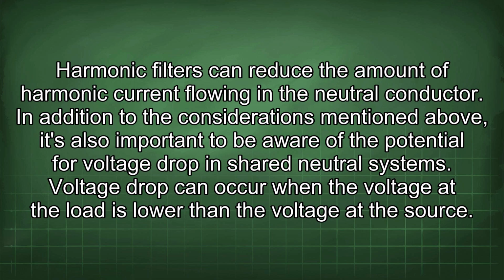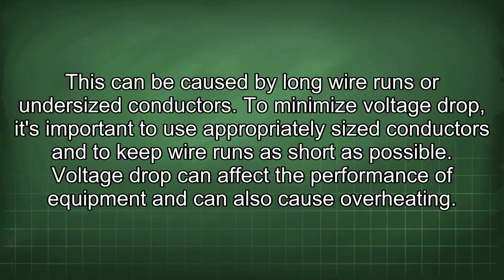In addition to the considerations mentioned above, it's also important to be aware of the potential for voltage drop in shared neutral systems. Voltage drop occurs when the voltage at the load is lower than the voltage at the source. This can be caused by long wire runs or undersized conductors. To minimize voltage drop, it's important to use appropriately sized conductors and to keep wire runs as short as possible. Voltage drop can affect the performance of equipment and can also cause overheating.